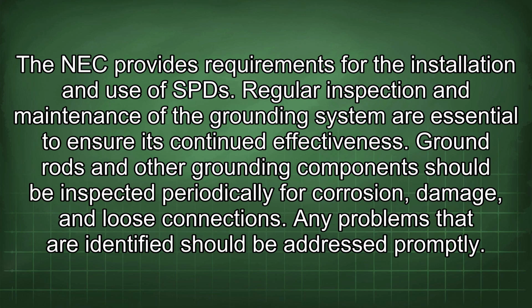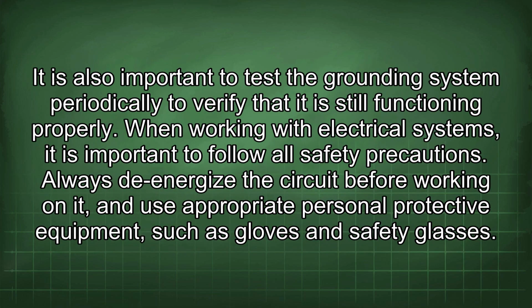Regular inspection and maintenance of the grounding system are essential to ensure its continued effectiveness. Ground rods and other grounding components should be inspected periodically for corrosion, damage, and loose connections. Any problems that are identified should be addressed promptly. It is also important to test the grounding system periodically to verify that it is still functioning properly.